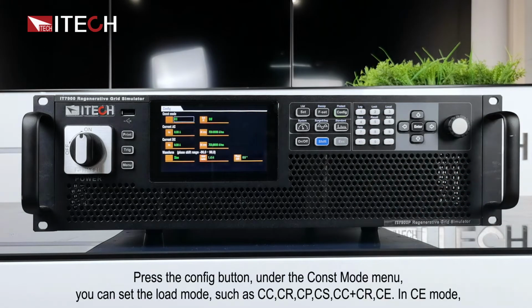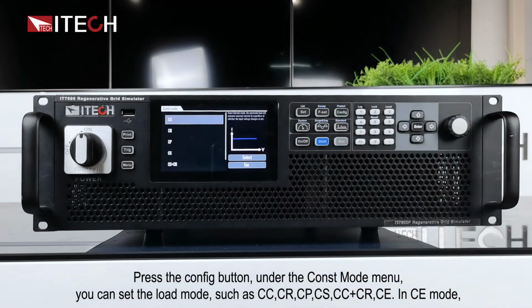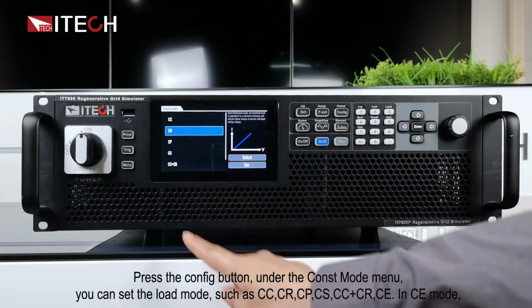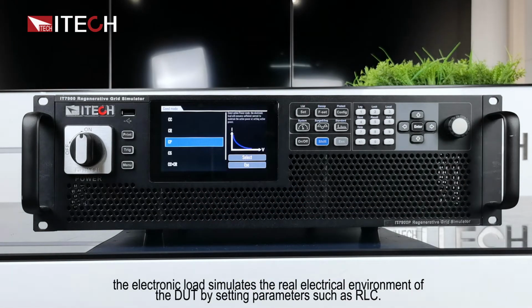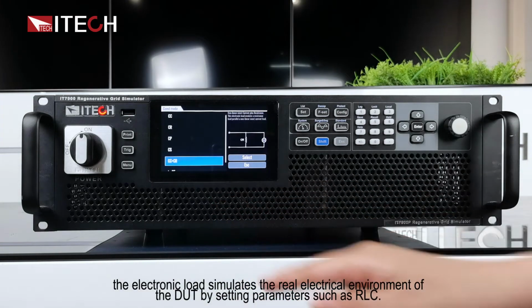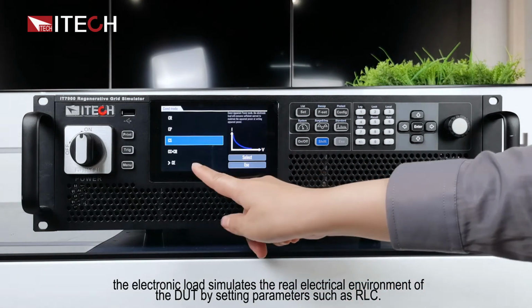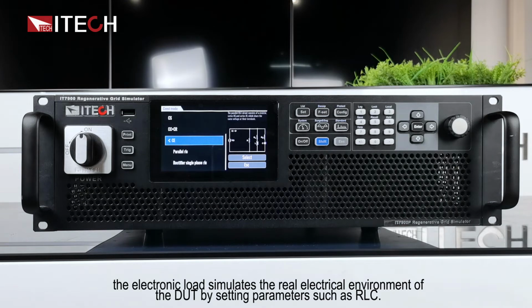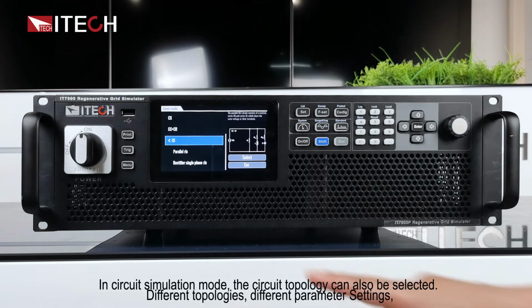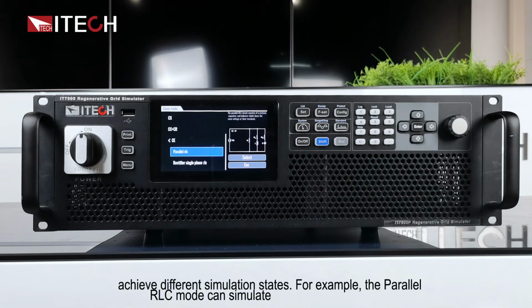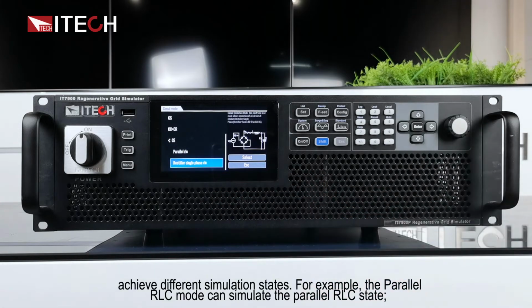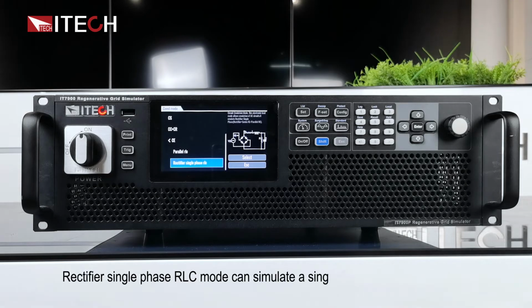Press the Config button. Under the Const Mode menu, you can set the load mode, such as CC, CR, CP, CS, CC+CR, CE. In CE mode, the electronic load simulates the real electrical environment of the DUT by setting parameters such as RLC. In circuit simulation mode, the circuit topology can also be selected. Different topologies, different parameter settings, achieve different simulation states. For example, the parallel RLC mode can simulate the parallel RLC state. Rectifier single-phase RLC mode can simulate a single-phase rectifier RLC circuit.